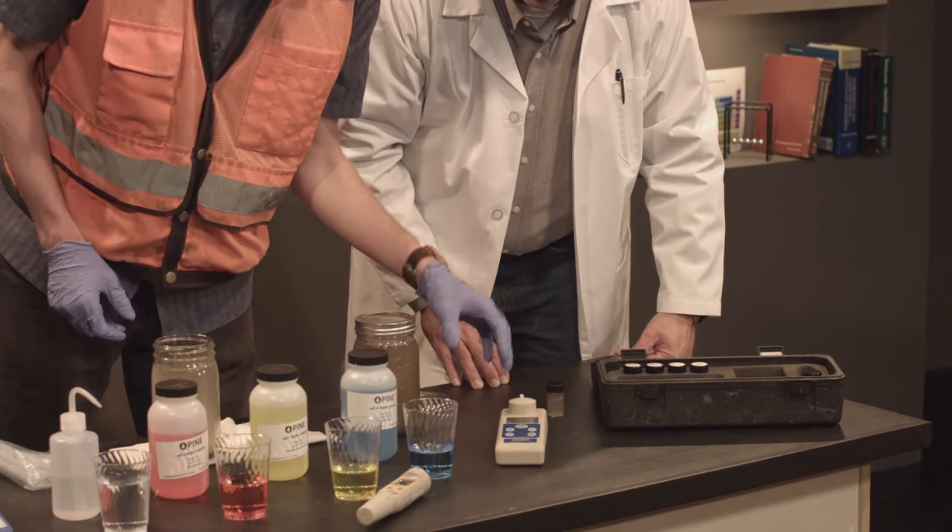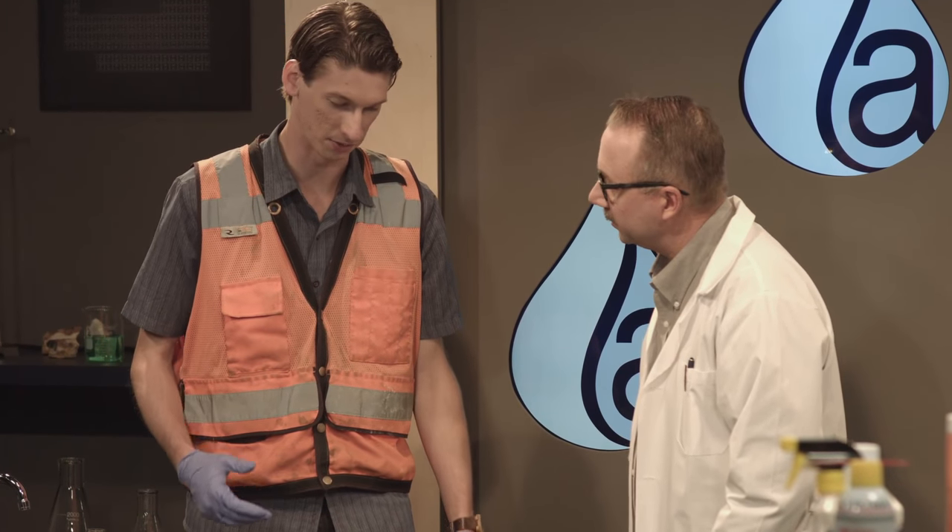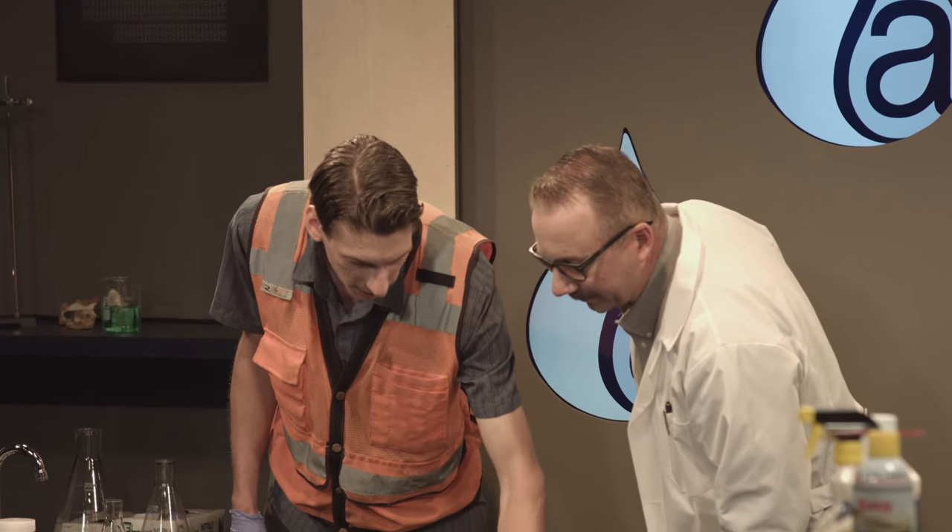We've got a second sample. Just make sure you get the fingerprints off. The reason we go through all these steps with the cap is because they are light sensitive — if you have light bleeding through, it will completely throw off your reading. We've had some inspectors come back saying their numbers are really good, and then you look at their meter — they don't have caps on.